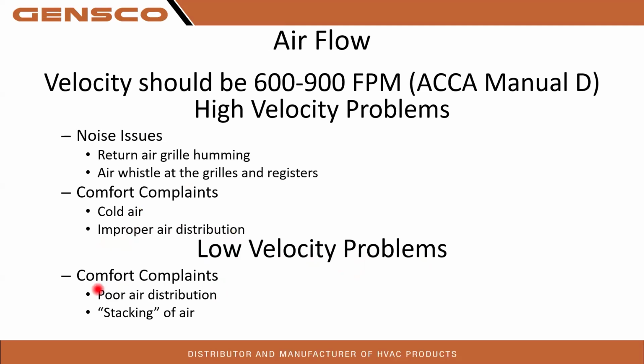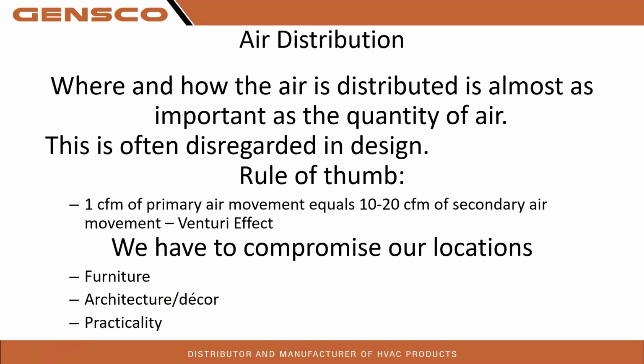Low velocity problems: if we don't have enough air, it's not going to comfort the area as well. Poor air distribution, stacking of air. It's just not throwing it all the way and reaching the ceiling for full circulation. Air distribution, where and how the air is distributed, is almost as important as the quantity of air. This is often disregarded in design, but we want 1 CFM of primary air movement per 10 to 20 CFM of secondary. So we have to compromise our locations due to furniture, decor, practicality, window settings, right?